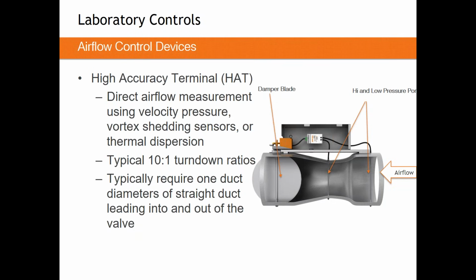Now there is regain in the aft portion of the valve, so the total drop across a high accuracy terminal is about 0.3 inches. So it's still a bit higher than a VAV box, but it's not that full 2 inches that the sensor needs to see.